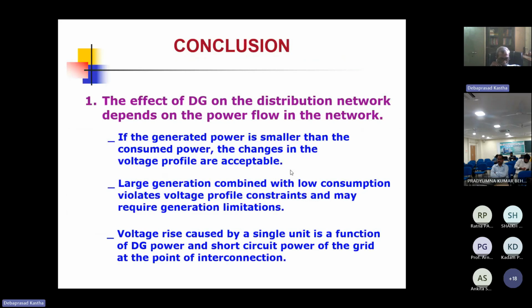So coming to the conclusion, the effect of DG on distribution network depends on the power flow in the network. If the generated power is smaller than the consumed power, the changes in the voltage profile are acceptable. That is if your DG is small size. But large generation can cause voltage profile and frequency problems.